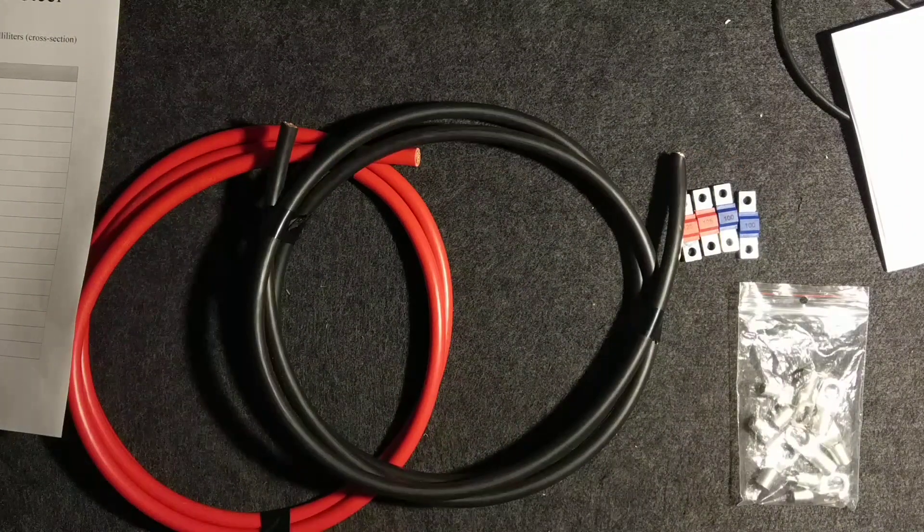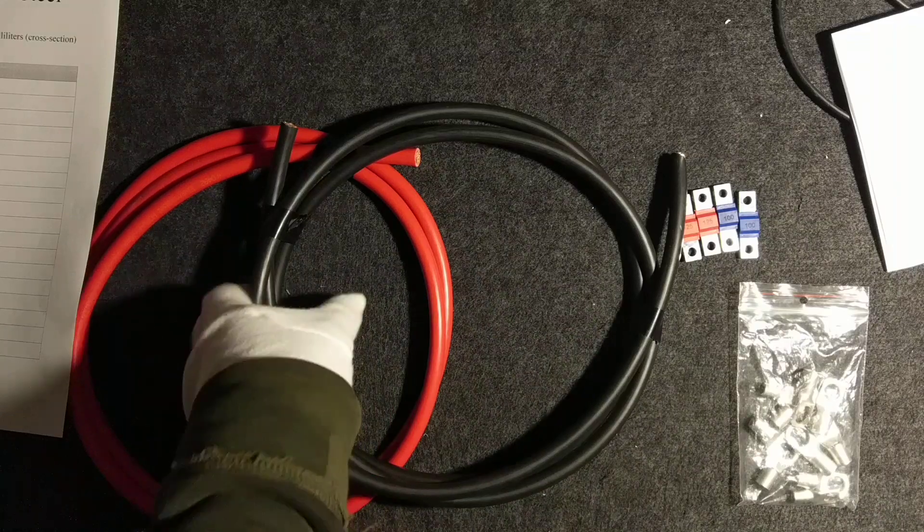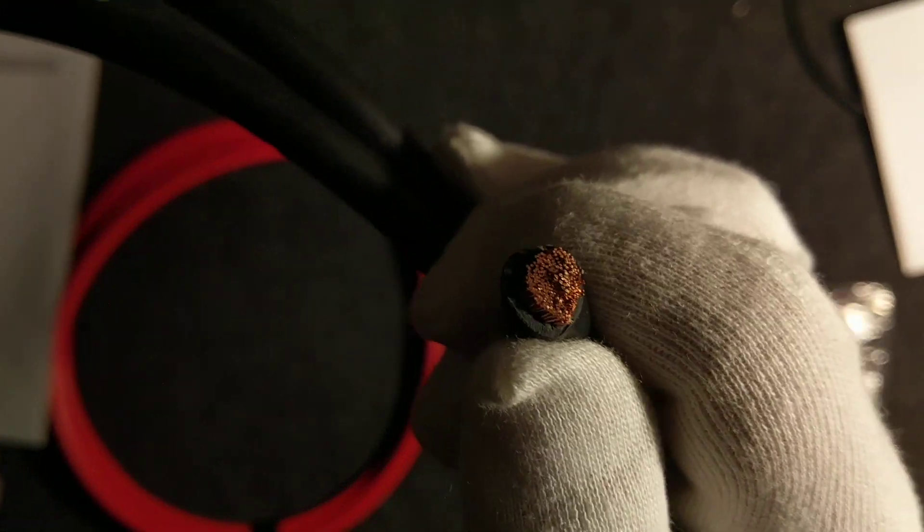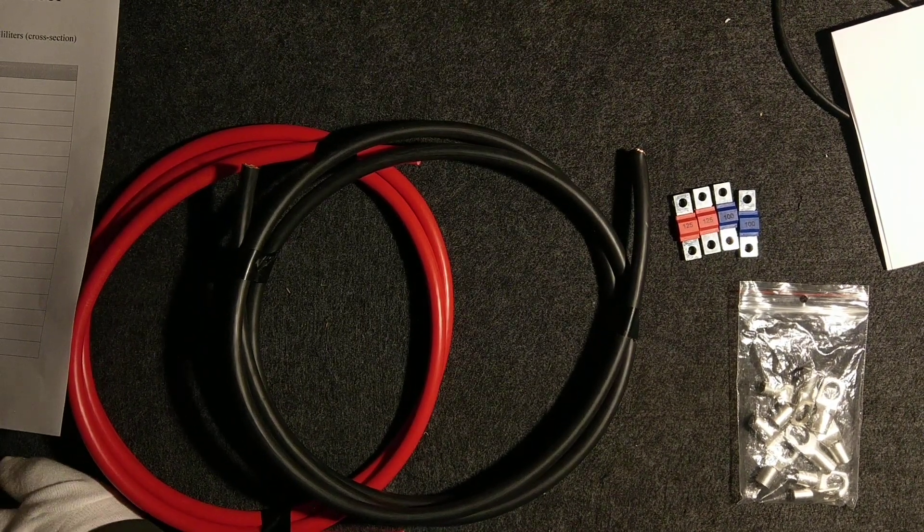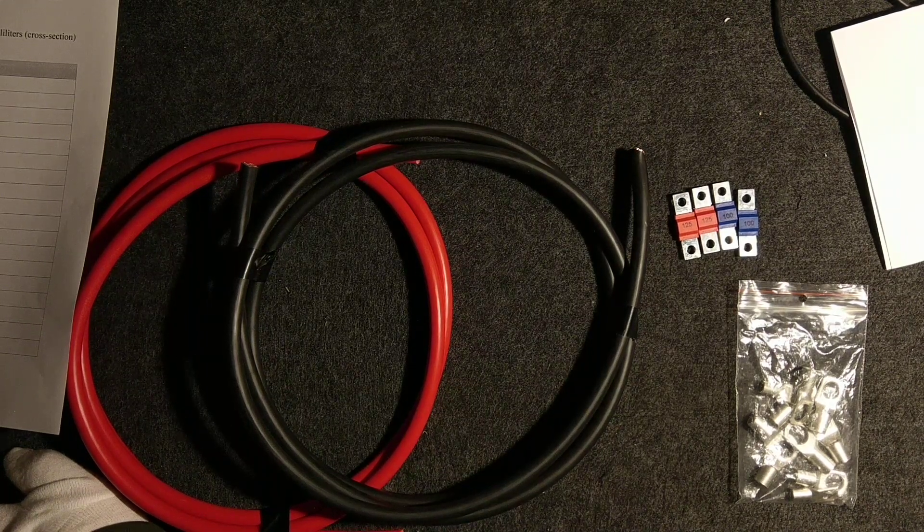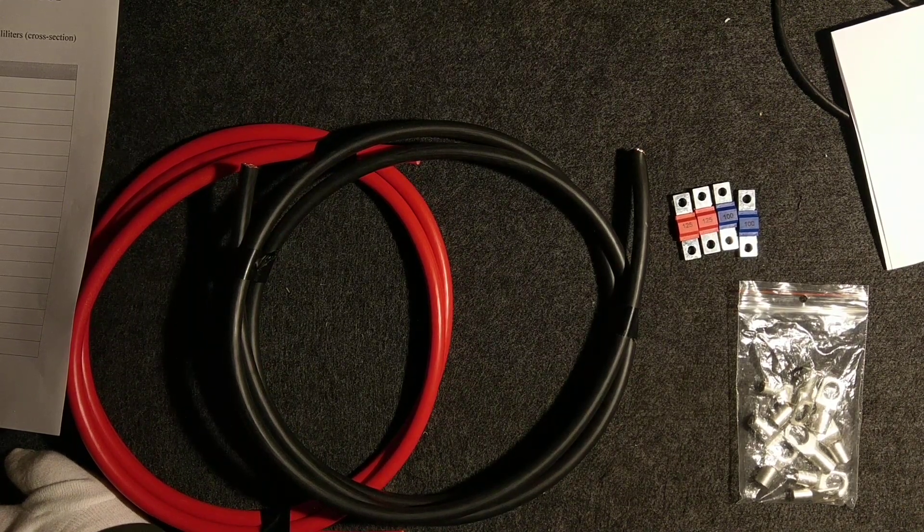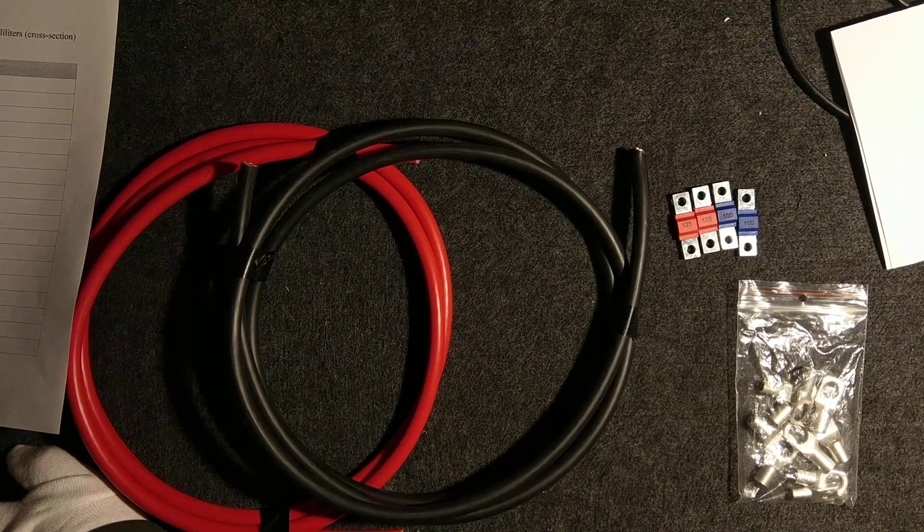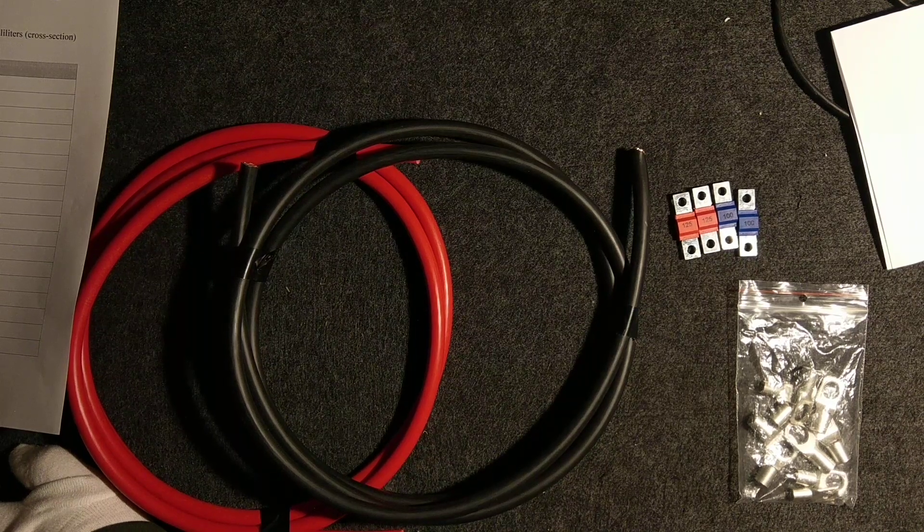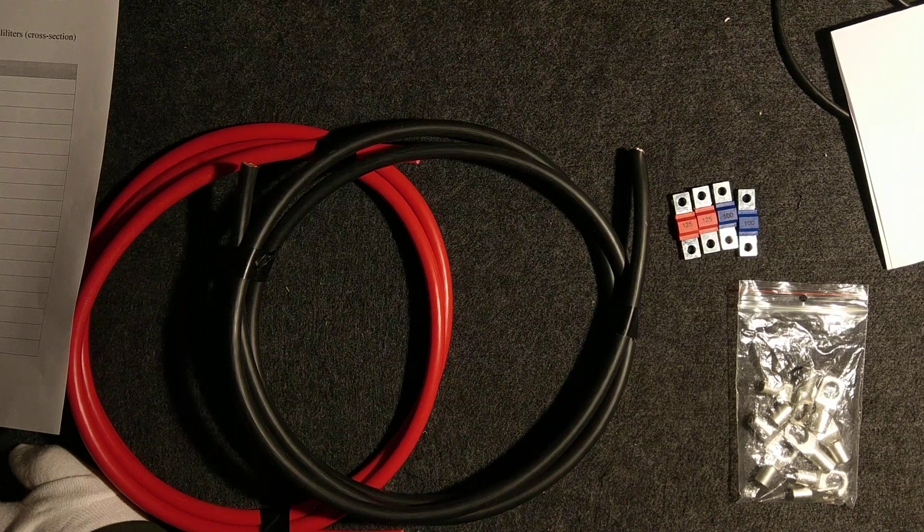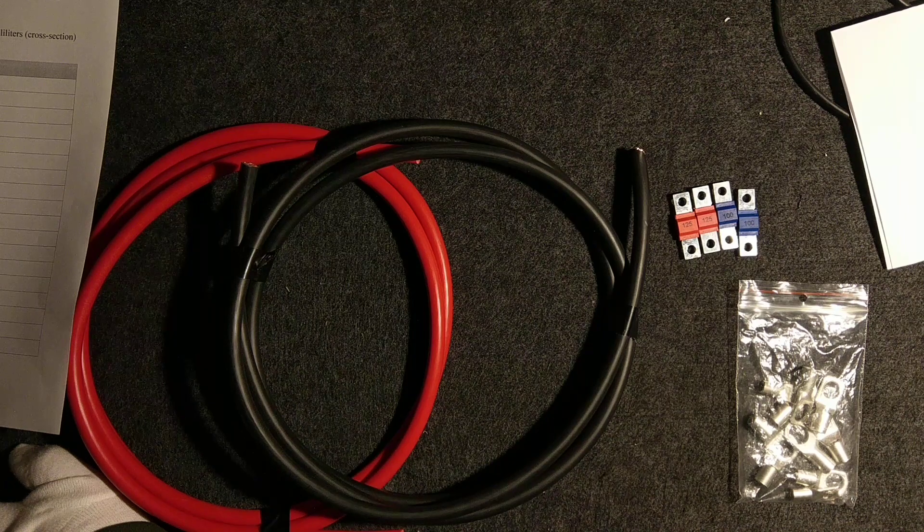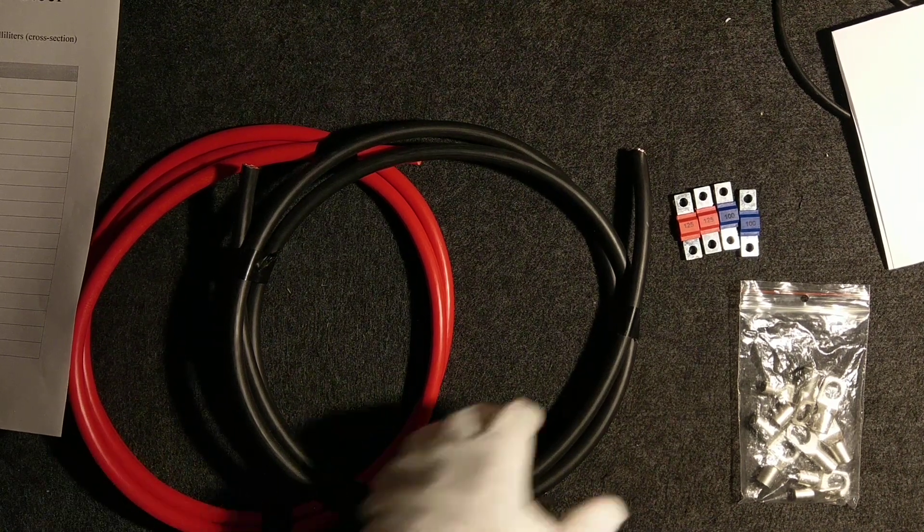It's called welding cable, and as you can see, it's a very thick copper cable. This is the cable which will be mostly used in 3 kilowatt and 5.5 kilowatt systems where the battery is 48 volts, because if you divide 5,500 over 48 volts, you will get 113 amps, and it also gives you a similar result.